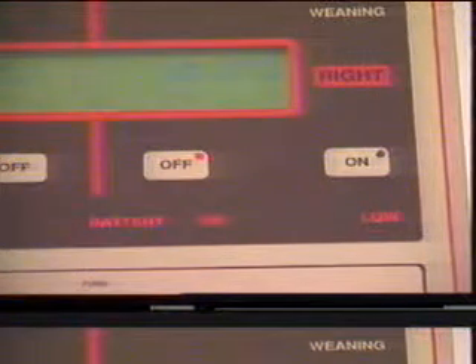In addition to safety alarms, the BVS system provides the operator with 3 backup systems in the event of emergency. Battery operation is automatically activated upon loss of AC power and is indicated on the front panel via a battery on message. An intermittent 2-beep signal is sounded to alert the operator. 1 hour portable operating time is provided with fully charged batteries. Whenever the batteries are less than 80% charged and the console is plugged into an AC outlet, a battery charging indicator is displayed. The battery low alarm activates when the console has less than 10 minutes of portable operating time remaining.